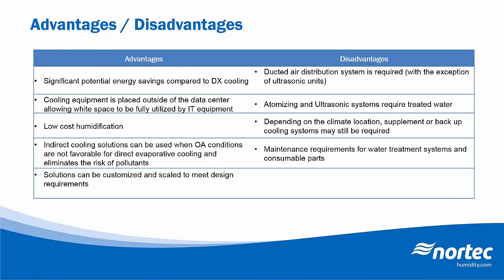We looked at indirect cooling solutions as well, and these can be used to provide low cost cooling in areas where direct evaporative cooling may not really be feasible due to the outdoor air conditions, or if there's a risk for outdoor air pollutants. And the last advantage here is that adiabatic systems can also be customized or scaled to meet design requirements. Large capacity systems are better suited towards potentially the evaporative media systems or high pressure nozzle systems. Those are easily scalable to 1,000 to 3,000 pounds an hour systems depending on the data center requirements.